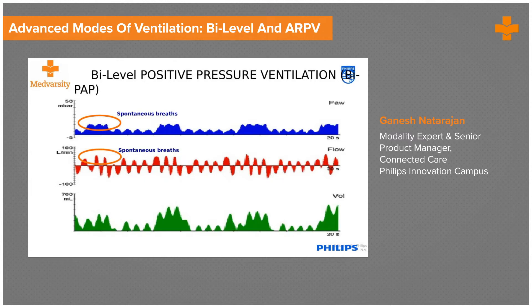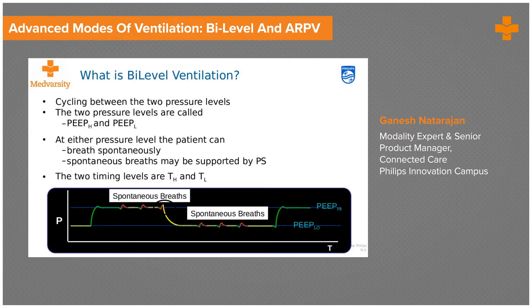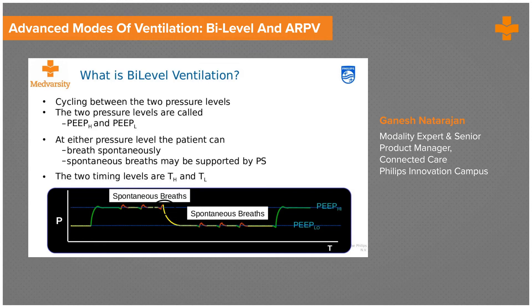Bi-level positive airway pressure is essentially pressure control ventilation with the ability to breathe anywhere in the cycle — that is the key difference from conventional PCV. When a spontaneous breath occurs in bi-level, you still have the IPAP and EPAP, and each effort is spontaneous. A trigger can be set at each pressure level, and a pressure support can also be set. At either pressure level the patient can breathe spontaneously, supported by pressure support, and if the patient is not breathing spontaneously it works like a timed mode.